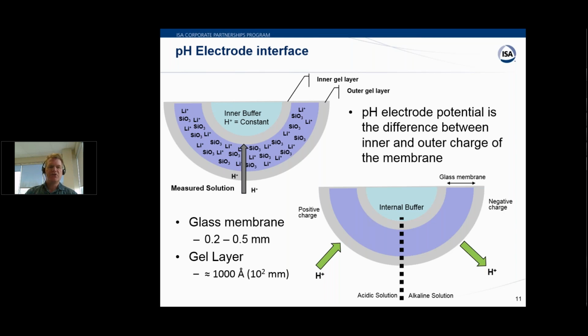So how does the pH electrode itself work? And you can see here on the left we have a cutaway of the pH electrode. And so what we're measuring is the potential, the difference between the charges on the inside and the outside of this glass membrane. And on the glass membrane we have a gel layer, which is typically about 1,000 angstroms, and so not very thick, and therefore easily damaged or sheared off. And you can see that the glass itself is made of a combination of lithium and silicon-based compound.